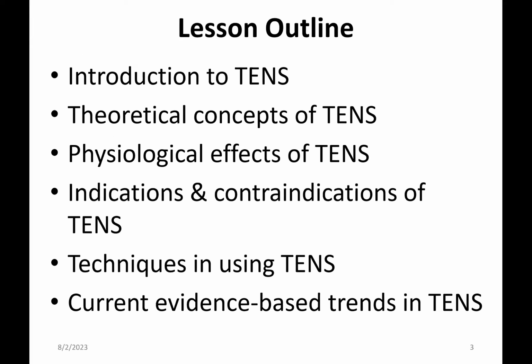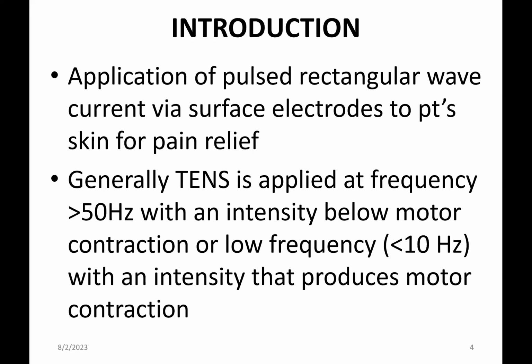So by definition then, TENS is the application of pulsed rectangular wave current using skin electrodes that are applied to a patient's skin for purposes of pain relief. And typically, TENS will operate on a frequency range of 1 to 150 hertz.